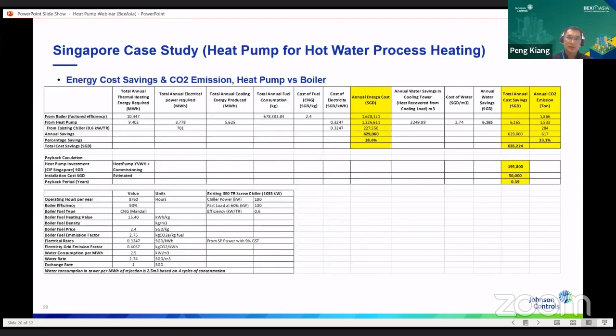We can see something like a 38% cost saving, which translates to quite a large amount of energy if you look at the cost of the fuel. And with the kind of carbon saving, we are saving something like 33% of the carbon footprint of the boiler fuel using natural gas versus that of the electricity grid from Singapore Power. So these two savings are significant for us towards a step of lowering the energy costs of the fuel and also the carbon footprint. And in terms of the payback, it's quite interesting as well. Depending on the type of heat pump we are choosing and selecting, we are seeing less than a year payback. So it's very, very attractive for us to really go forward with these heat pump case studies.